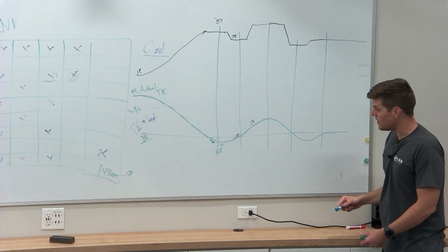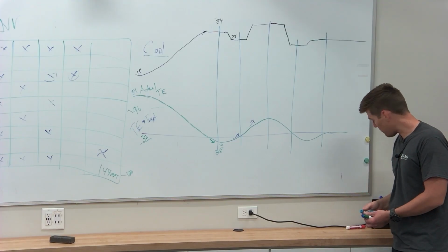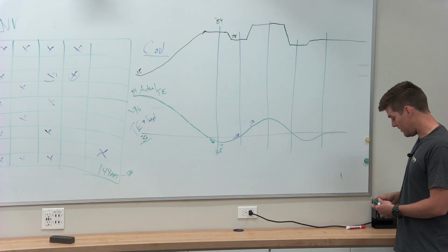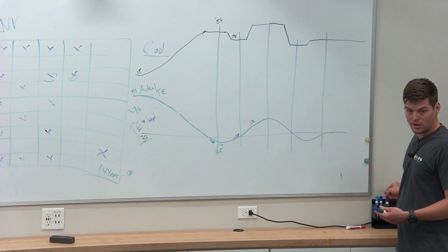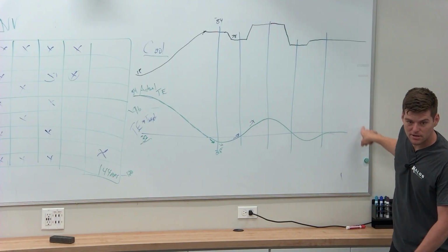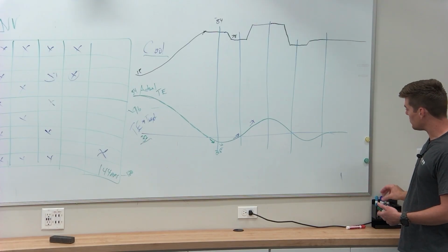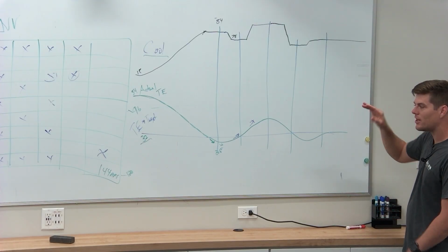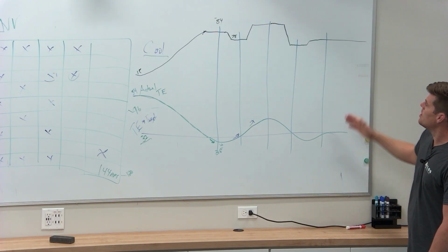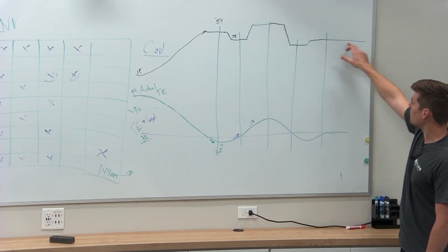And ideally, in a perfect world, when the system runs for a while, this is why I tell you guys you have to give it 30 minutes, right? Because you've got to get out of this first until the demand levels out and you actually get refrigerant flowing, and you get to a point where they actually start to touch, or they dance a little bit on top of each other until it levels out and you get nice level numbers.